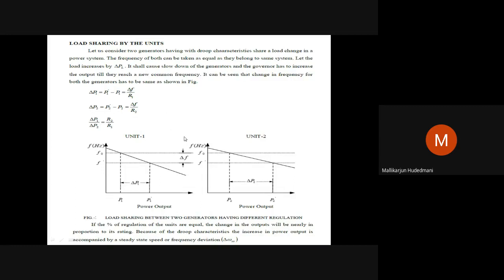Next, how will this happen when we have a number of generators acting in a station sharing the load? This is called load sharing by different units in a plant. Imagine in a station there are 2 to 4 generators, all running, and we have purchased machines 1 and 2 from some continent, machines 3 and 4 from our own India, and we are putting all 4 together in parallel, and their characteristics, like regulation characteristics, are different.